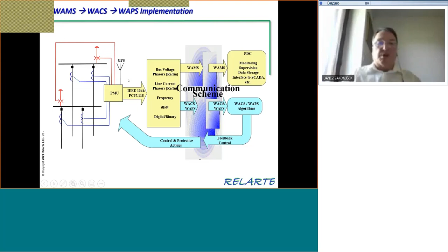We have special protocols, so we are transmitting voltage phasors, current phasors, frequency value, rate of change of frequency, and digital or binary signals if you want. The wide area monitoring system just gives monitoring and supervision of data storage. It has interface to SCADA and so on, but the wide area control system and protection system operate over certain algorithms within the power system, and they send back feedback, protection and control actions, to the substation where they are used.